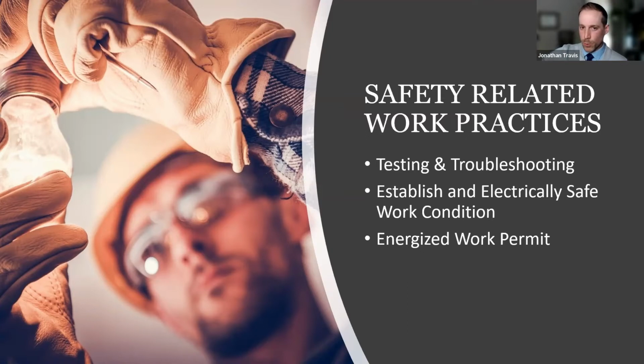When the energized work permit really comes into play, what this says is we know that people don't die of a shock if everything is turned off. And we also know people won't be in an arc flash if everything is turned off. Therefore, we are going to turn everything off as much as possible. Sometimes there will be jobs that need to get done that arguably you could turn it off. Let's just say changing fuses.